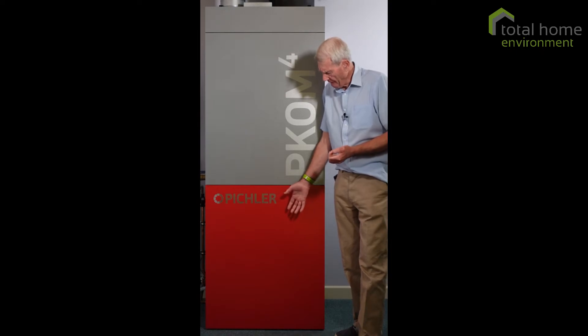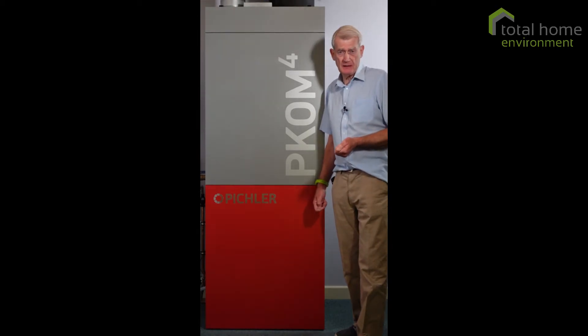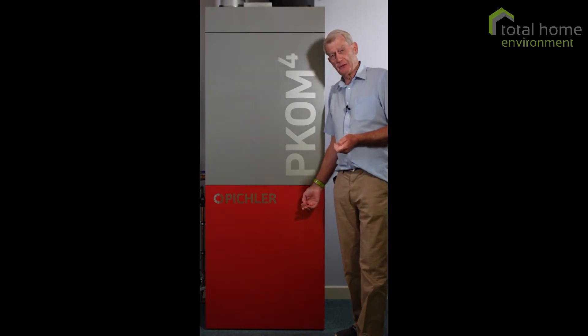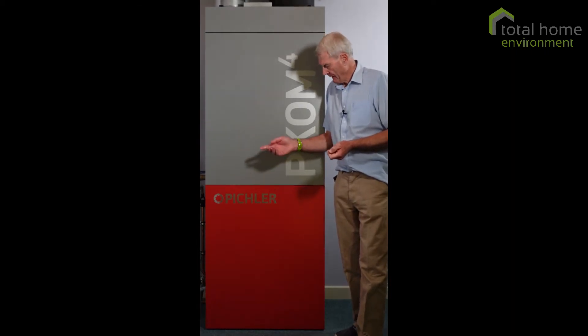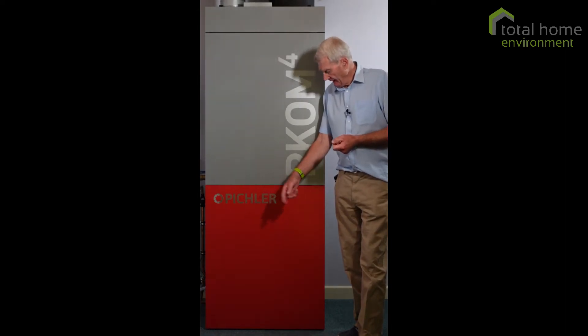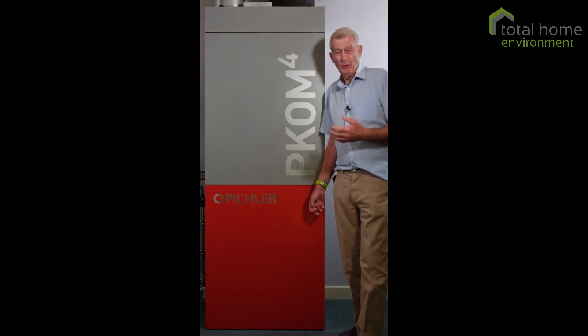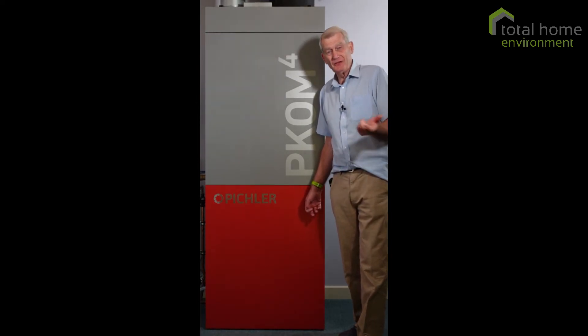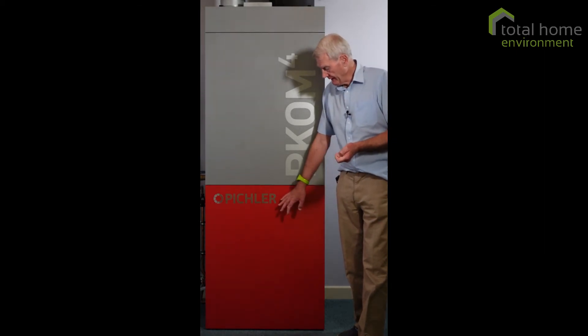Below that we have our water cylinder. It's an indirect water cylinder — 212 litre capacity — and it can heat the water to a maximum of 65 degrees centigrade. Part of the water cylinder has an internal coil, which is an additional heat exchanger whereby you can introduce into or export out of the cylinder additional heat. It's a really nice feature.